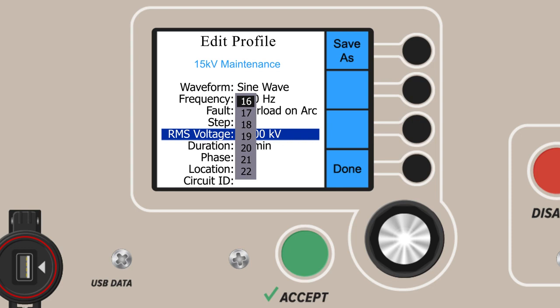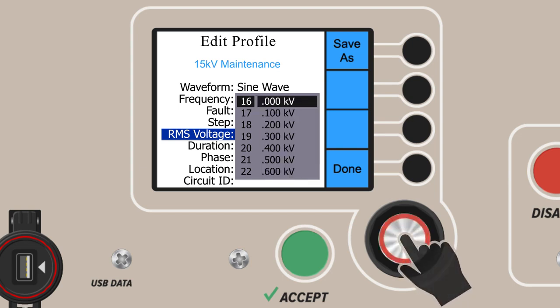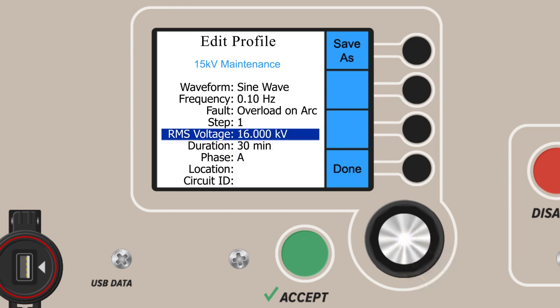For example, we'll choose 16 kV RMS here, the appropriate voltage for the maintenance of a 15 kV cable. There are also decimal units for the voltage. You can add or select voltage to the 10th of a kV. We'll keep our voltage at 16 kV RMS.